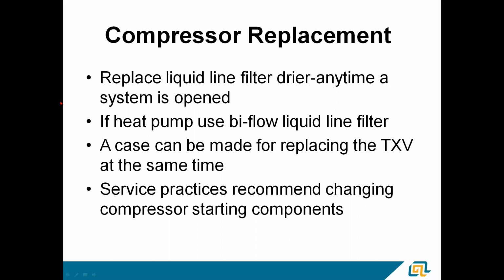Honestly, if you're replacing a compressor and the system has a TXV, I can make a very strong case for replacing the TXV at the same time. If you come up to a system with a failed compressor, you really don't know why that compressor failed. So if you have a TXV that's underperforming, it's driving up that superheat, put a new compressor in, you really haven't addressed the TXV issue. If you don't want to replace the TXV, if you say, there's a lot of extra work, don't want to charge the consumer, whatever, at least take very, very accurate startup data when you fire that new compressor. Verify your superheat is correct. So, just take that extra step.